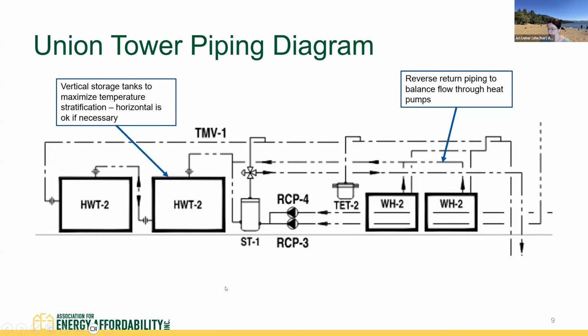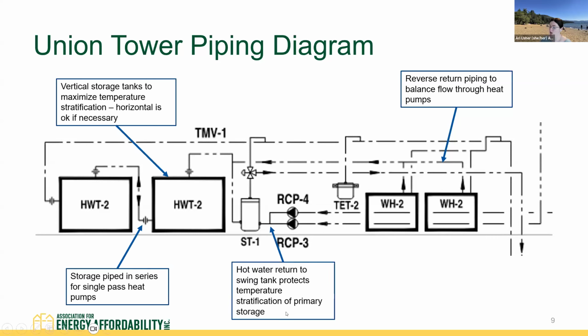And then vertical storage tanks are always recommended. It's going to maximize the effective storage of our tanks, but horizontal storage tanks are okay if necessary. In certain cases, they may be needed for the project, and they work just fine as well. Then we see that the primary storage has got to be piped in series for a single pass heat pump, and that the hot water should be returned to the swing tank rather than to the primary storage, again, to protect the stratification of the storage.